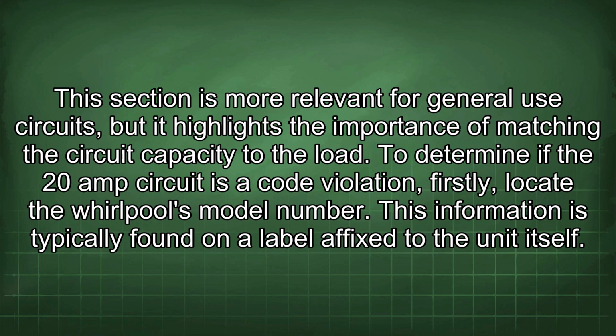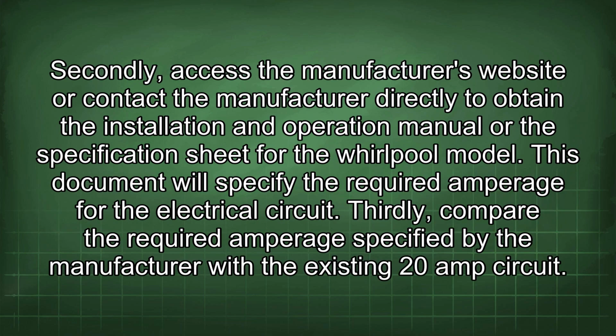To determine if the 20 amp circuit is a code violation, firstly, locate the Whirlpool's model number. This information is typically found on a label affixed to the unit itself. Secondly, access the manufacturer's website or contact the manufacturer directly to obtain the installation and operation manual or the specification sheet for the Whirlpool model. This document will specify the required amperage for the electrical circuit.